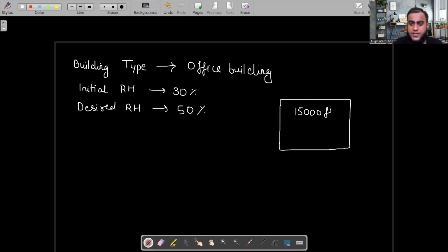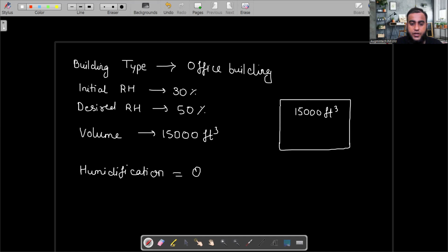Total volume, suppose, let's say, 15,000 cubic feet. I'm considering that. So the volume of space is what? 15,000, because this detail you will get from the drawing. 15,000 cubic feet I have considered. Now tell me, to calculate the humidification load, what is the formula? Airflow rate Q into W2 minus W1 into 4.5 factor.